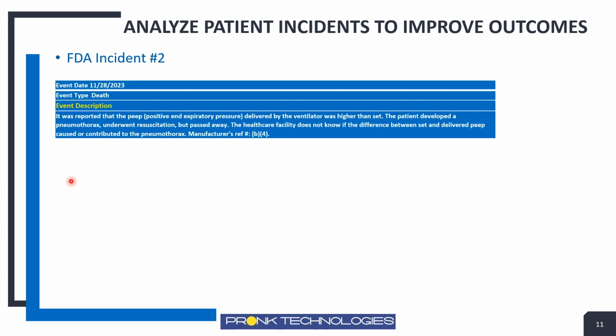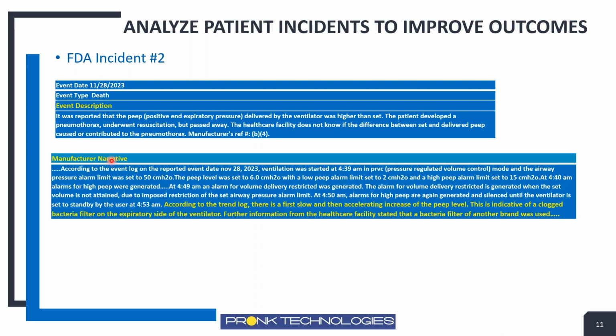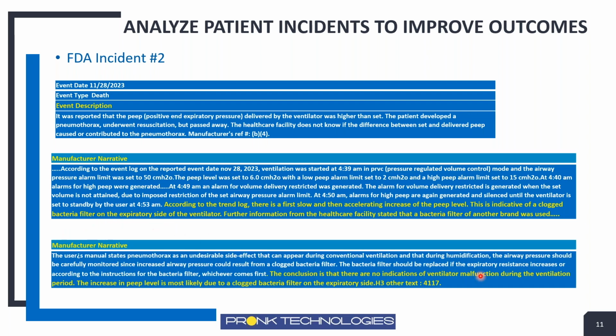One more incident, we have an issue here where the PEEP pressure, the positive end expiratory pressure, was increasing on the patient to the point where the patient experienced a collapsed lung, basically, and unfortunately the patient expired. Again, they did the investigation. They could see through the logs that the PEEP alarms were sounding, letting the clinician know that there were alarms occurring. They could see in the trend logs that the PEEP pressure was increasing and increasing, and there was an indication that there was some kind of clog in the bacterial filter on the expiratory side. They did conclude that the ventilator did not have any malfunction. So technically speaking, the ventilator was performing properly. It was alarming properly. But unfortunately, because they missed where a bacterial filter became clogged on the expiratory side, it built up that PEEP pressure and caused harm to the patient.